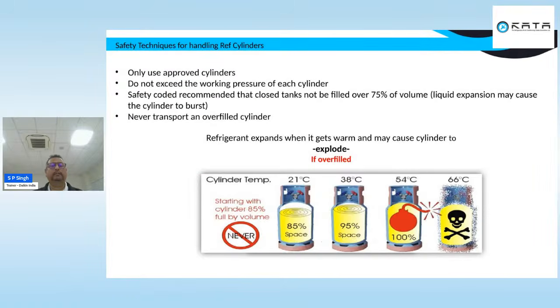So at last we can say, regarding the cylinder, here I have mentioned that we should never charge your refrigerant to 100%. It should be around 80%, and less than 90%. As you have seen here, if you are gradually moving from 85% to 95% and 100%, and your ambient temperature, where your cylinder has been kept, is also high, there is a possibility that when your cylinder is at 100% it will blast and explode. And when we are talking about a very high temperature, again it is very dangerous and can lead to casualty. So we have to take care.